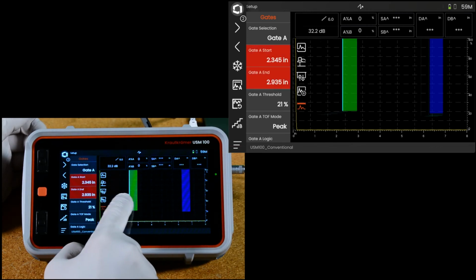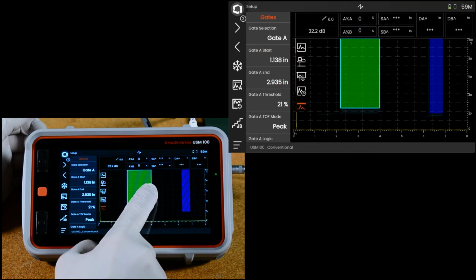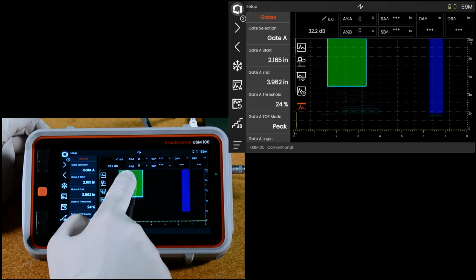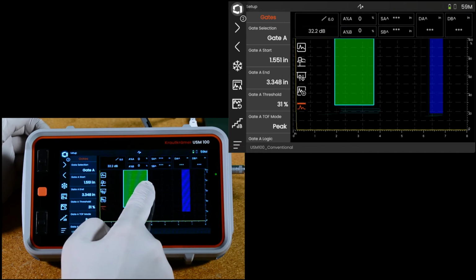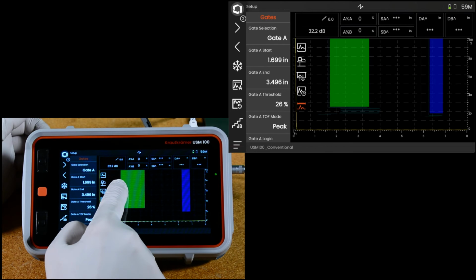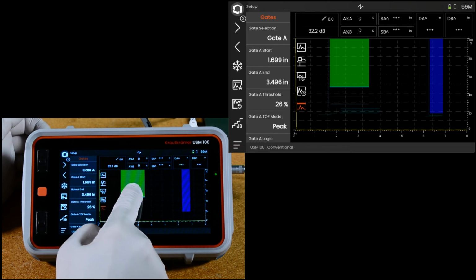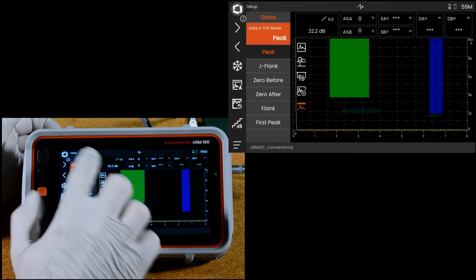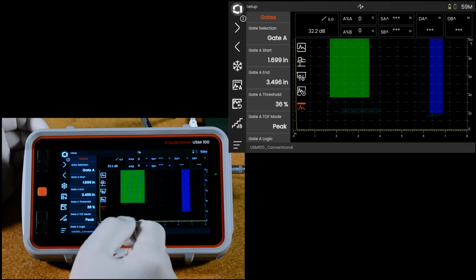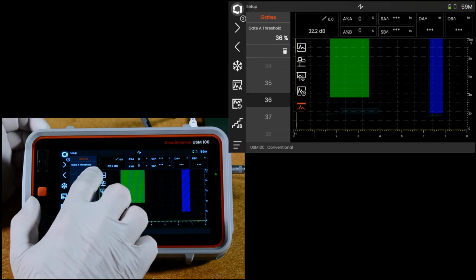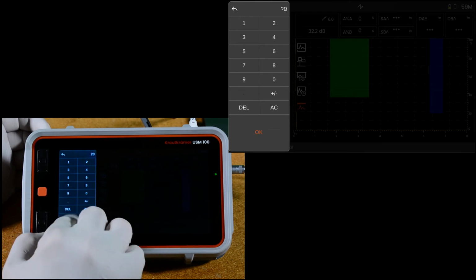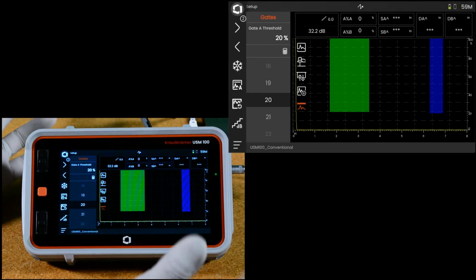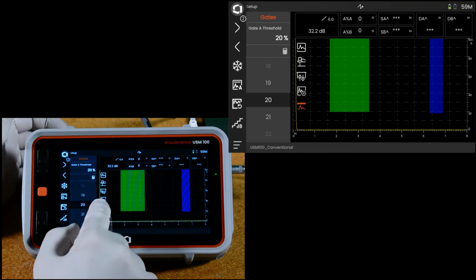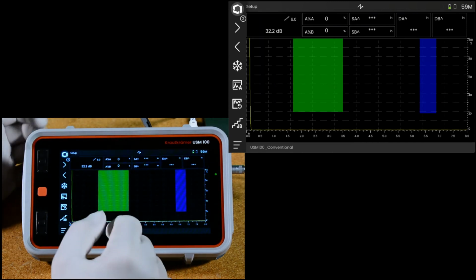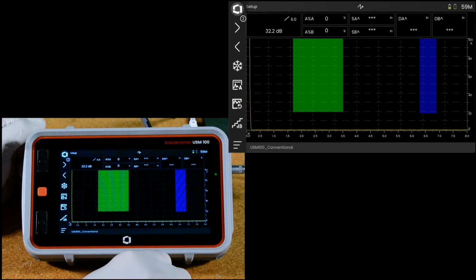You can set delay, width, and threshold all by simply grabbing one edge or the other edge of the gate itself, or grabbing just the threshold. And you see when you let up, the matching parameter moves as well. Or I can come in here if I just knew I wanted to set that straight to 20%. I can set it to 20% and everything synchronizes that way. Okay. So that's all the basic menu controls for the instrument.